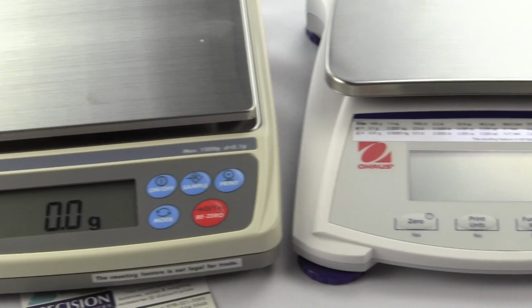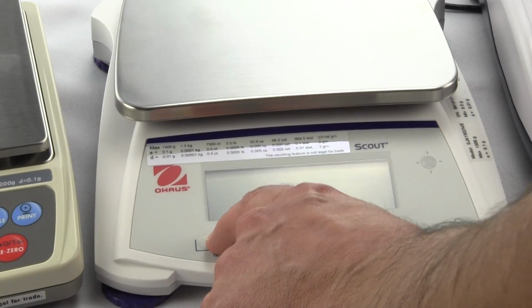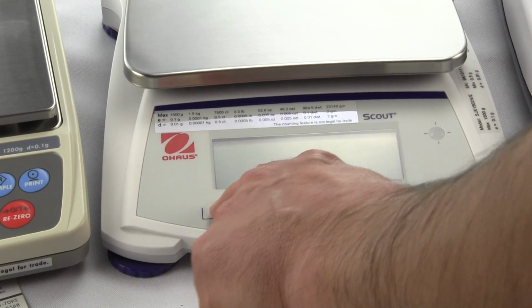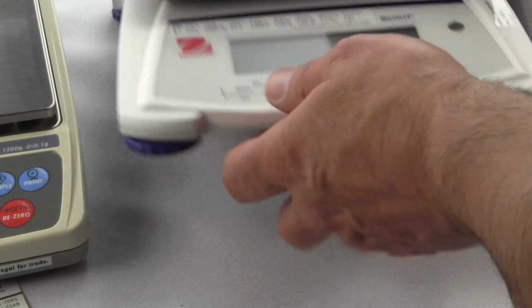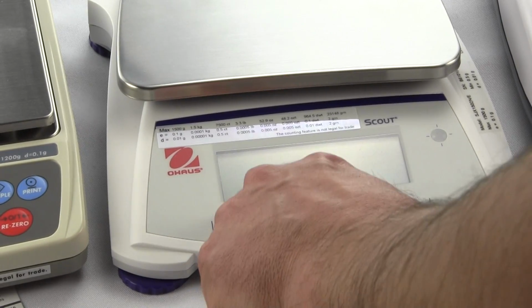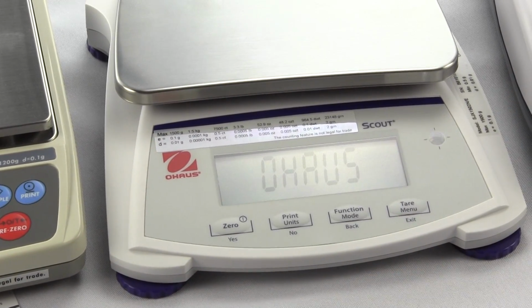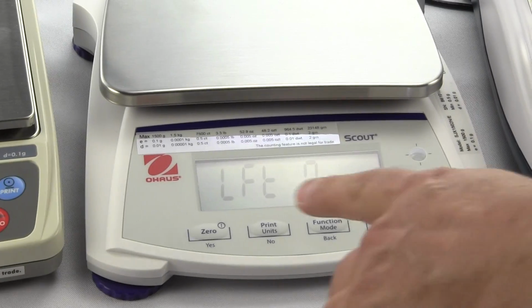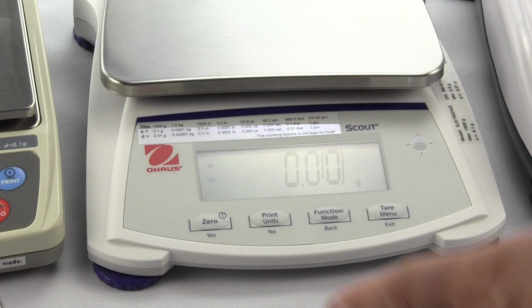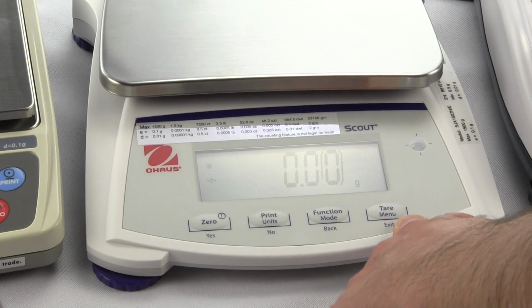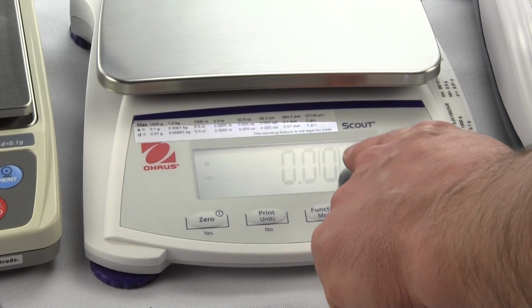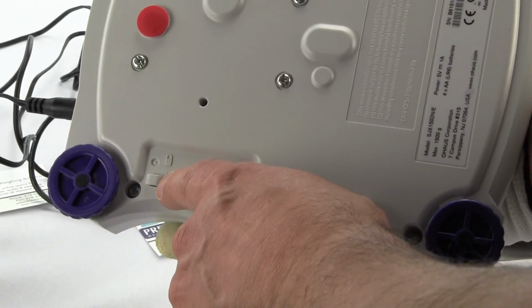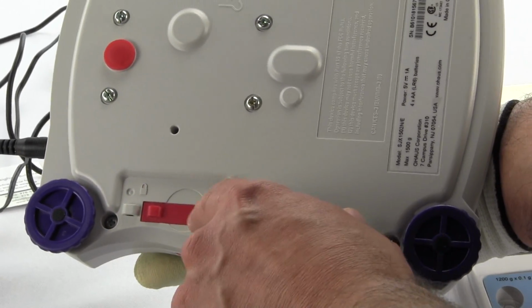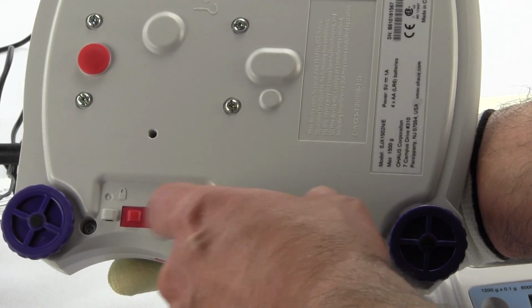Now we'll go to the Ohaus. On the Ohaus for calibration, all we're going to do is turn on the scale. So I have to plug this one in. Okay. So you'll notice on power up it says legal for trade on. If I try to go in to do a calibration with this scale, it's in the legal for trade mode. There's a bracket here. What I have to do first to calibrate the scale is, on the bottom of the scale, they call this a security lock. You'll see it's on lock. I have to slide it over and actually listen to hear the click to unlock.